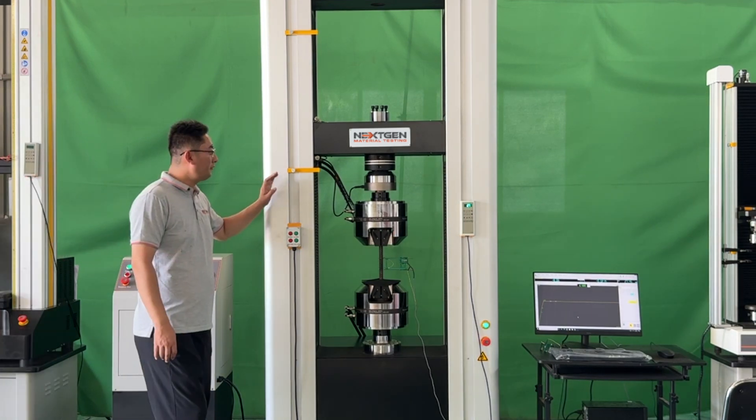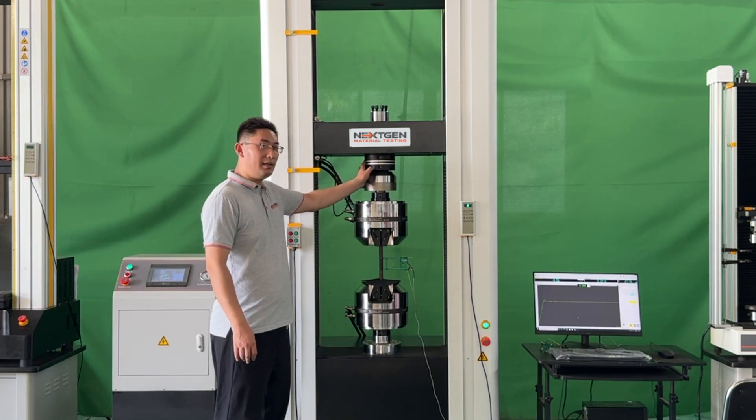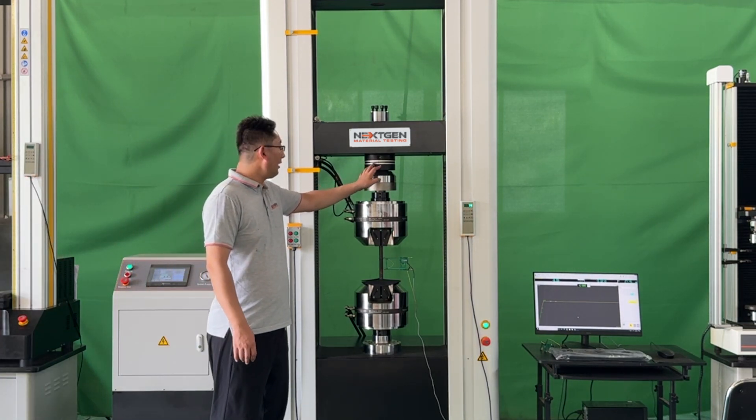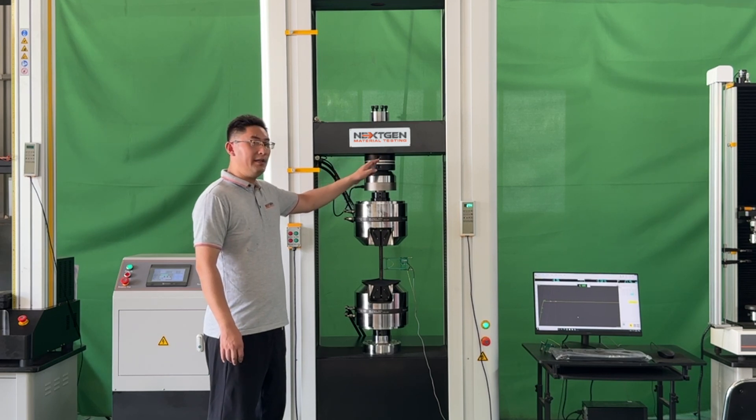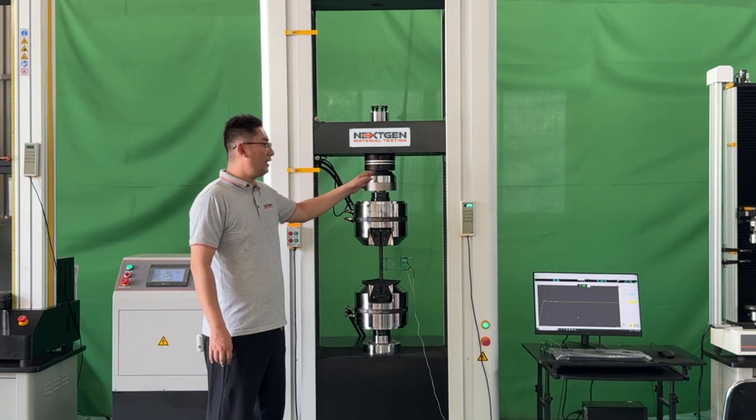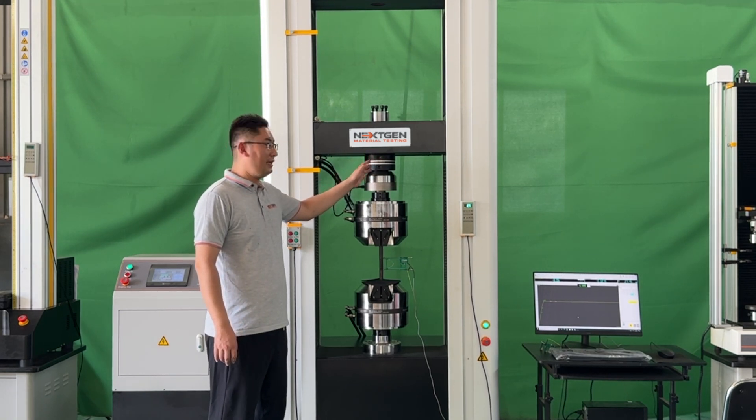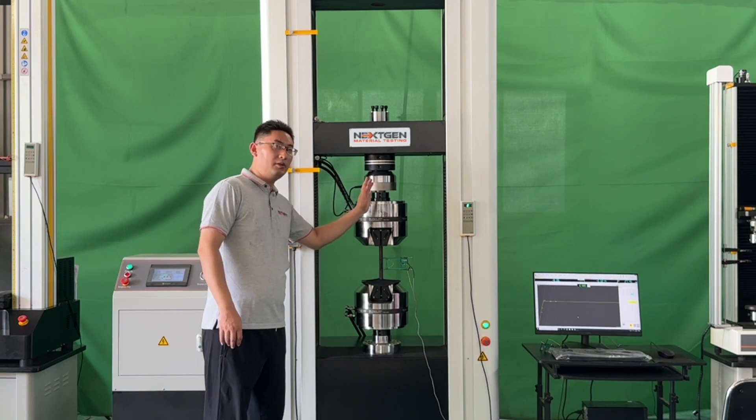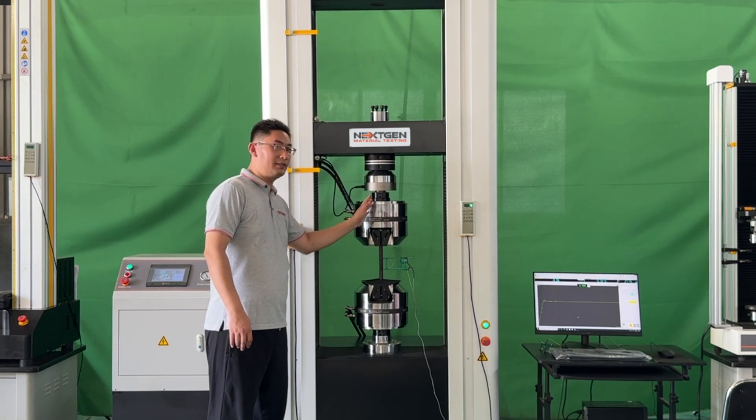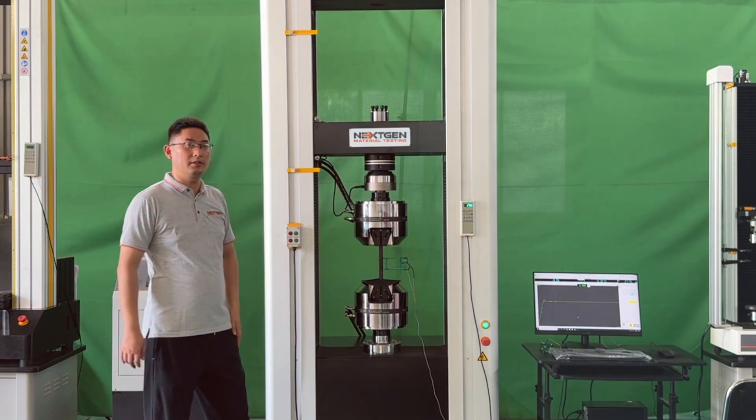This 300 kilonewton universal testing machine is equipped with an alignment device, precisely calibrated to meet NADCAP certification standards, making it an excellent long-term asset for manufacturing facilities, laboratories, and other testing environments.